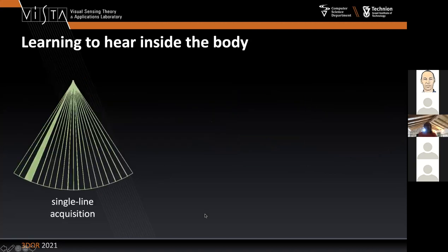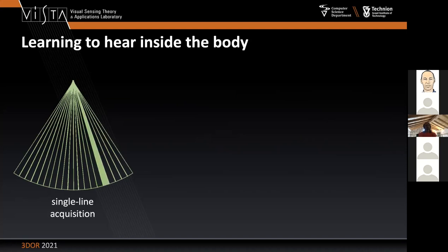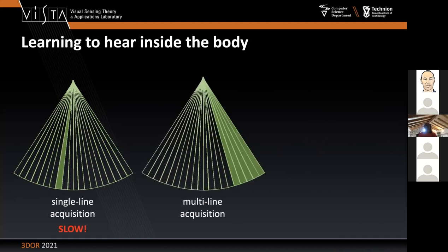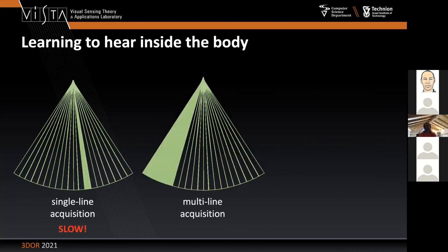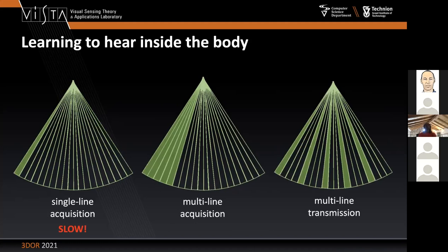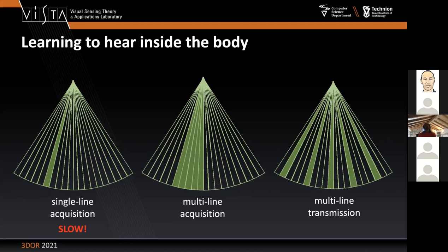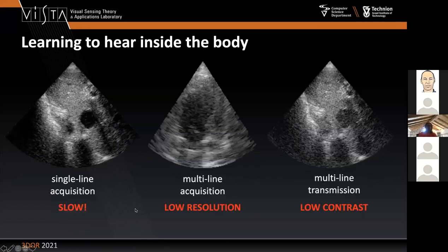The application we tried to deal with is imaging of fast-moving objects, like cardiac imaging. Regular ultrasound works by sweeping the scene with a focused beam, which can be prohibitively slow for fast-moving objects. There are two regular solutions: one is to defocus the beam and sweep faster — multi-line acquisition — or to send multiple beams separated by angular separation to acquire multiple echoes faster. But both suffer from artifacts: multi-line acquisition gives lower resolution, and multi-line transmission produces low contrast and many kinds of artifacts that are difficult to correct.